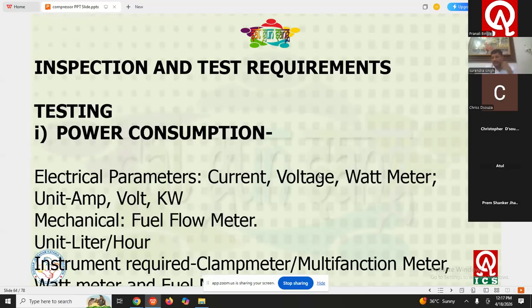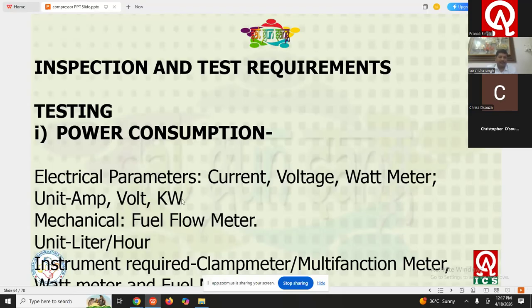Okay, now coming to the testing part, which parameter we have to monitor, what is the unit, what equipment you have to use, it's written here. So if we are going to check the power consumption, so we need to check the electrical parameters and then the power consumption. So current we need to witness, voltage, we need to witness the watt, that is power consumption. Unit is the ampere, volt, and the kilowatt is the unit respectively.